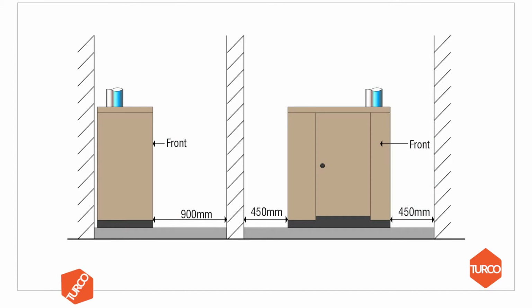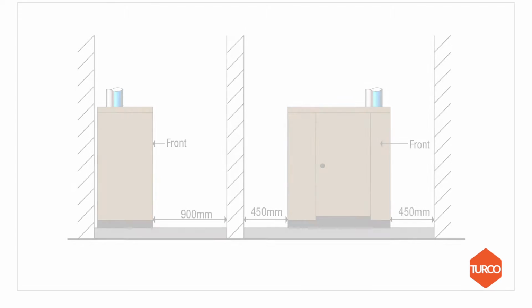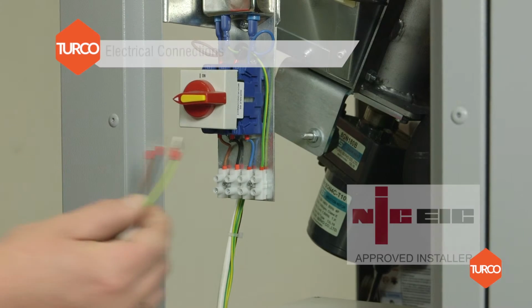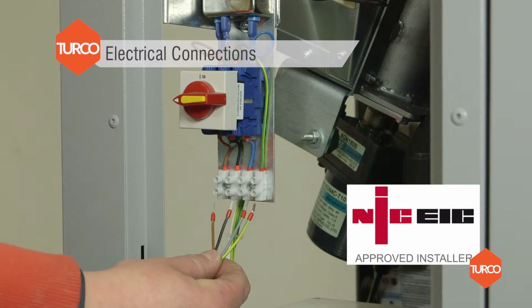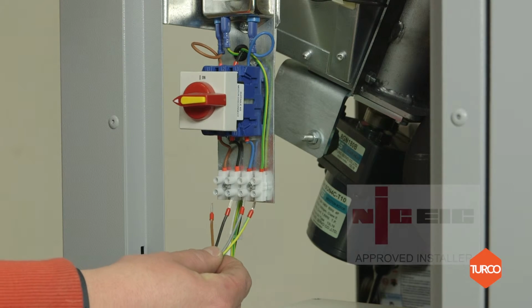On the 16 kilowatt model, the installer must leave enough space so that the user and service engineer can access the boiler routinely. This means leaving at least 900 mm at the front of the boiler and 450 mm at either side. Electrical connections. A certified electrician should carry out the electrical connections.